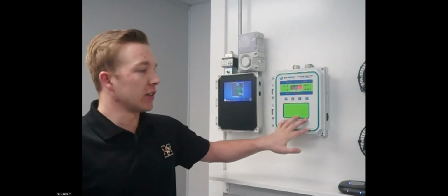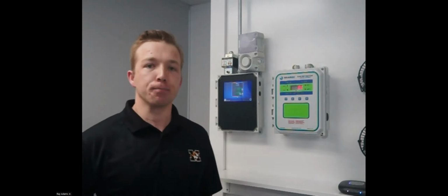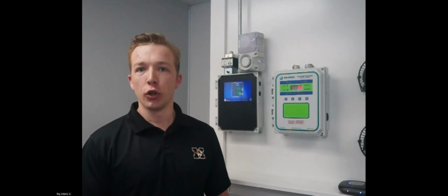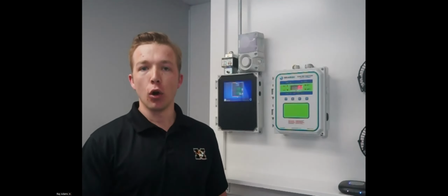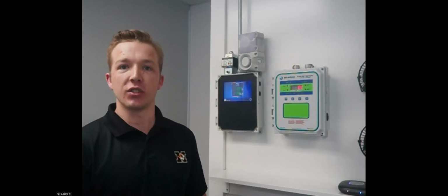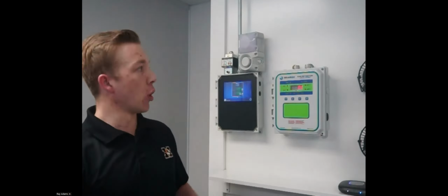But our standalone detector is designed around a 3-relay sequence of operation. Generally, in these smaller application jobs, you're going to see either a 2-speed fan or maybe just an individual single fan that you have tied into your detector. Sometimes you may have a second fan, and so you can have a low alert and a high alert to control 2 different fans, or a 2-speed fan if that's what they're looking at. Then you have a high alert value, or an alarm, I should say, that is designed to tie into a remote horn and strobe, maybe a fire protection system that's already in place. That's to say relay 1 and relay 2 did not flush the gas out fast enough, the gas levels continue to rise, and that's when your alarm would go off.